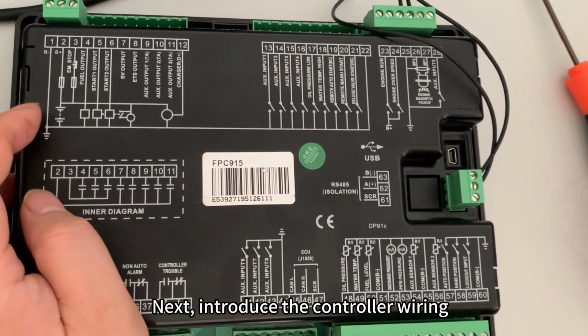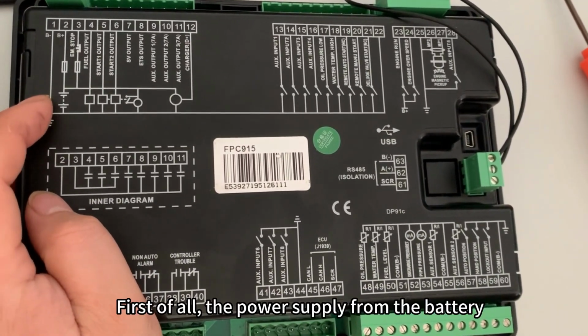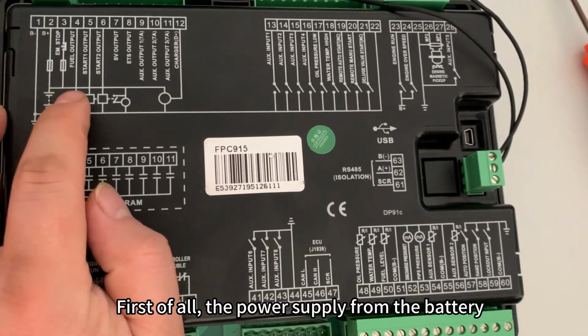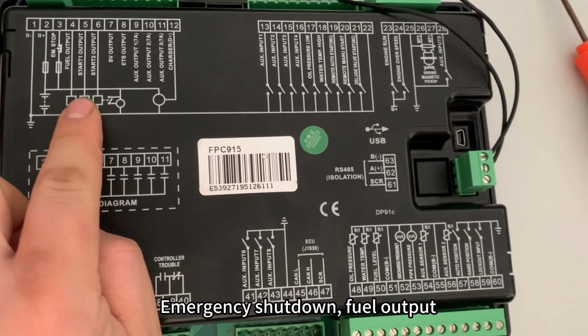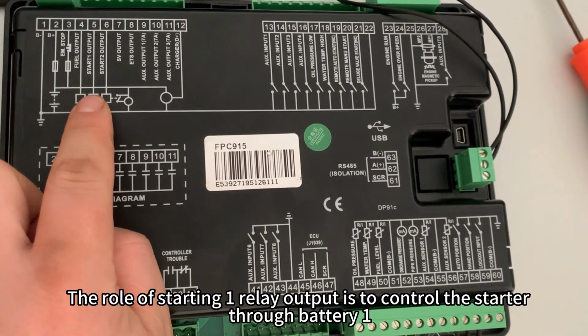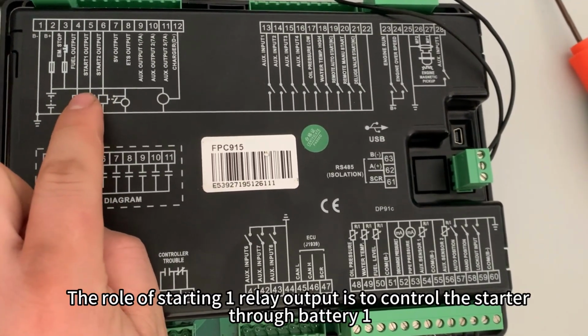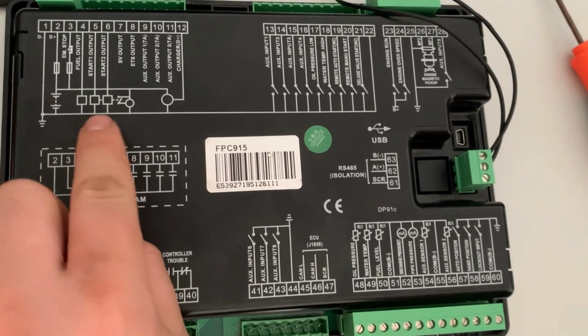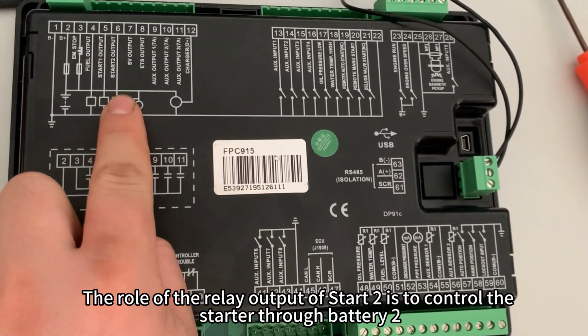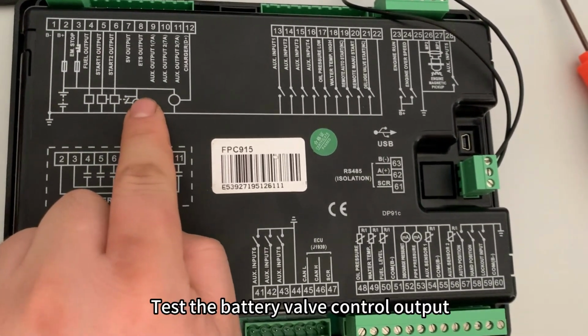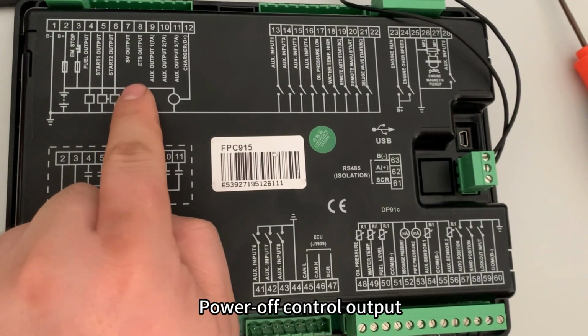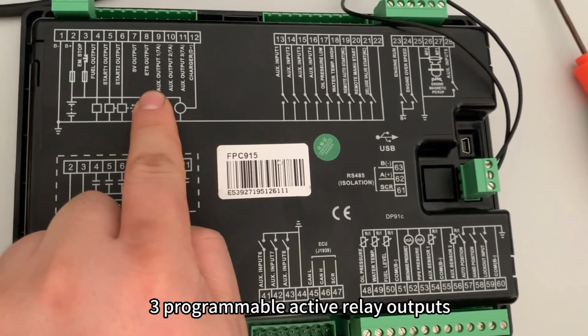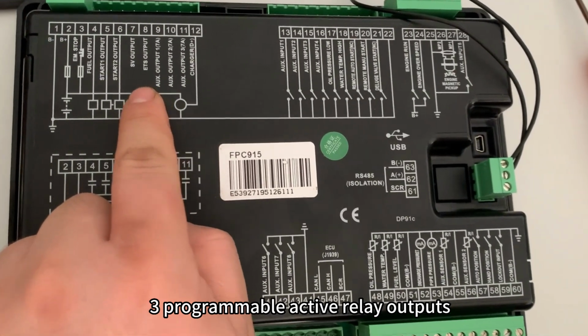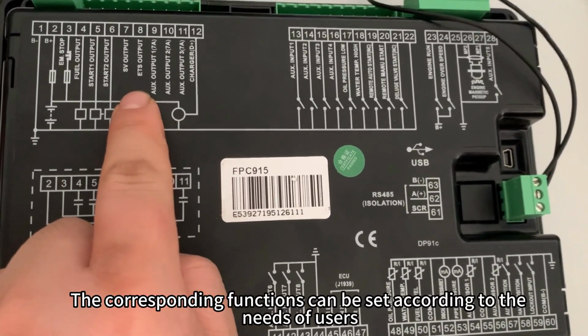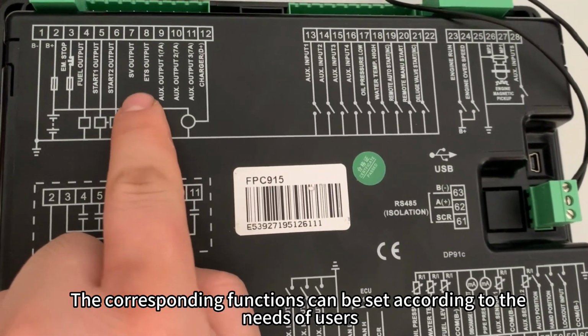Next, we introduce the controller wiring. First of all, the power supply from the battery. Emergency shutdown, fuel output. The start 1 relay output controls the starter through battery 1. The start 2 relay output controls the starter through battery 2. Test battery valve control output. Power off control output. Some programmable relay outputs. The corresponding functions can be set according to the needs of users.